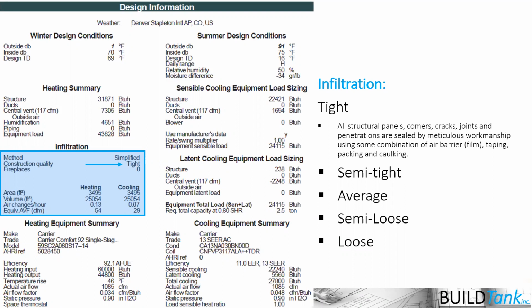So it's much better to actually use definitive data from blower door testing. If you're working with a production builder, for example, that's built 100 houses and tested 100 houses, you should have an air leakage rate average for that builder that would be much more accurate and better to use than this guesstimate process that's allowed in Manual J.